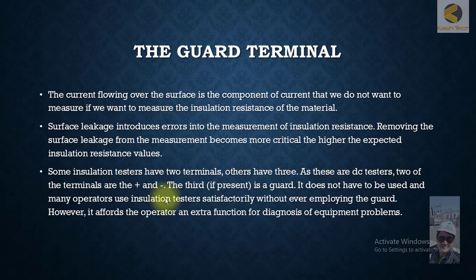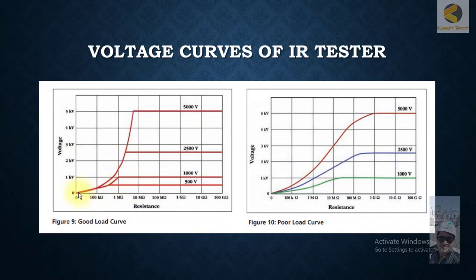Here they have shown voltage output of two different insulations when we are testing them. This is the voltage output where the insulation is good. You can see the voltage increases because in the start, because of charging current and high polarizing current, the voltage output is less. With some time it increases and reaches its maximum value, which is the applied voltage value, and then its curve is quite steep.